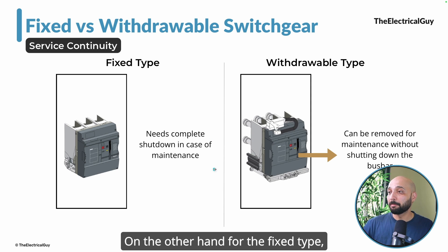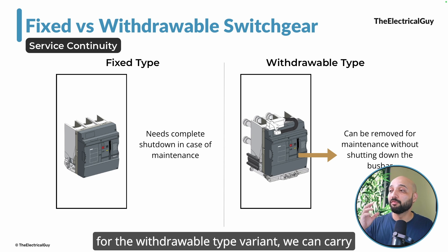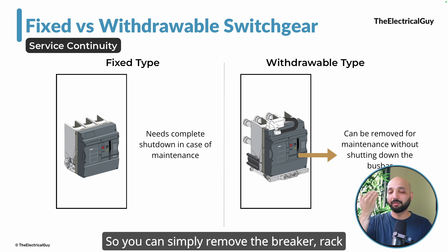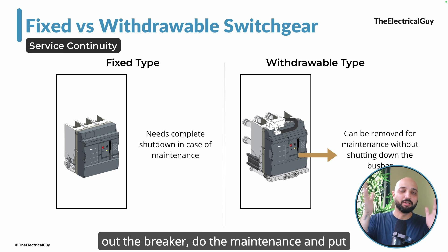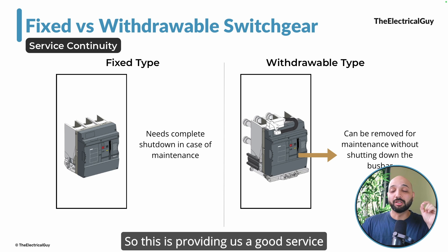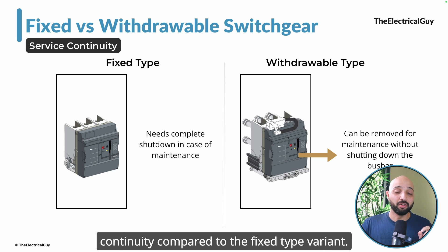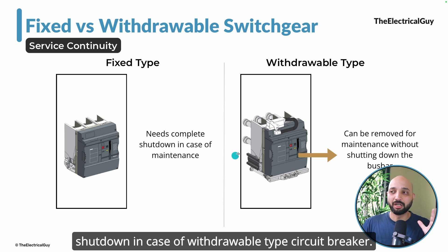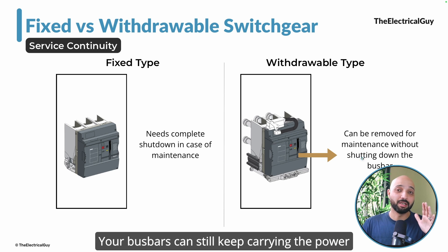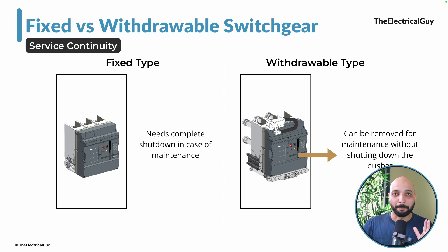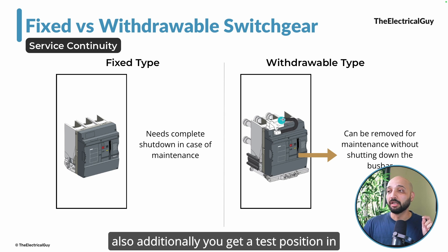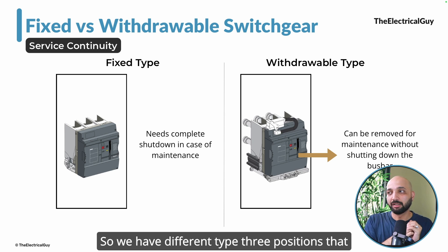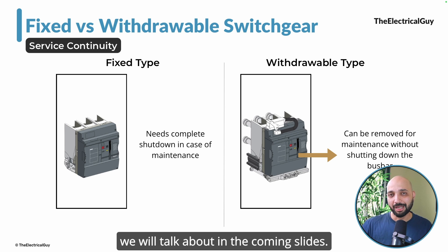For the withdrawable type variant, you can carry out maintenance without impacting other feeders — simply rack out the breaker, do the maintenance, and put it back. This provides much better service continuity compared to the fixed type; you do not need a complete shutdown, and the bus bars can keep carrying power. Additionally, the withdrawable type provides a test position — there are three positions that a withdrawable circuit breaker can offer, which we will discuss shortly.